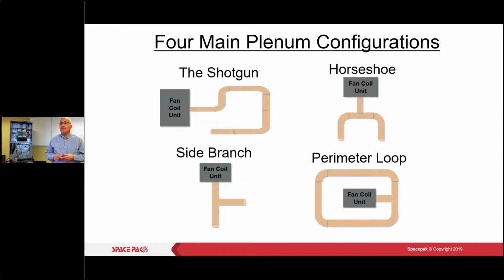The shotgun is the most common. You can see that we're coming off of the air handler, and we're trying to get our plenum to the edges of that attic space so we can make our drops. All right, we can do the horseshoe, which is another very common one. Side branch is also very common. And here's going to be a 60-40 split. All right. If you wanted to do any zoning on a side branch, you'd have to have your zone damper here. If you wanted to do something like that, we couldn't have our damper there. All right. And the perimeter loop, if you can really do a perimeter loop, now you've got a pressurized system. You should have equal airflow coming out of all the drops. All right. So try to get your plenum out there as close to the rooms.